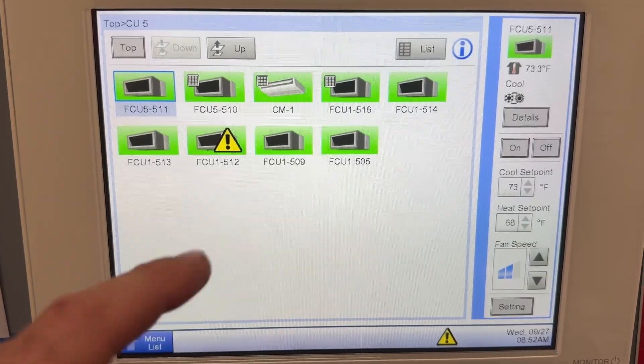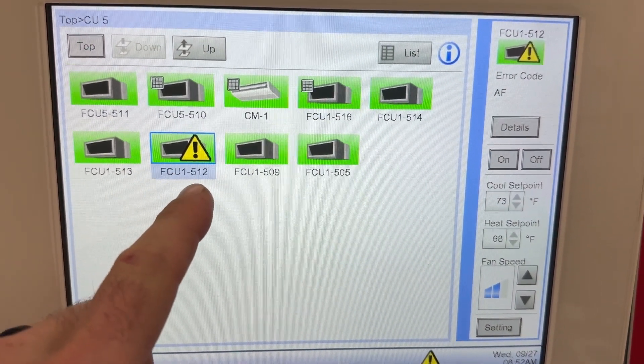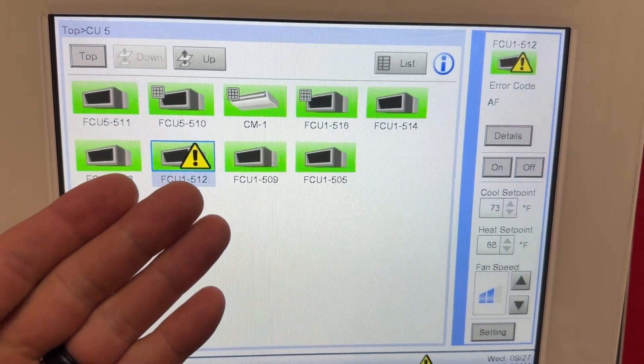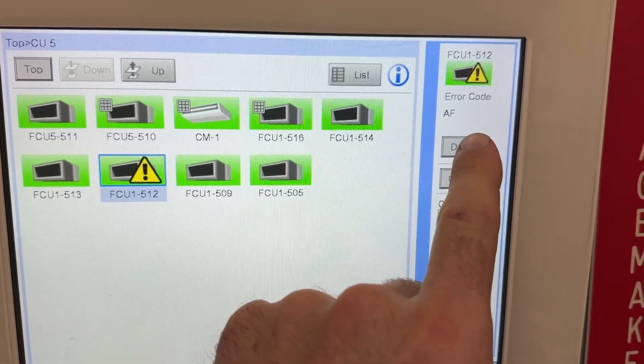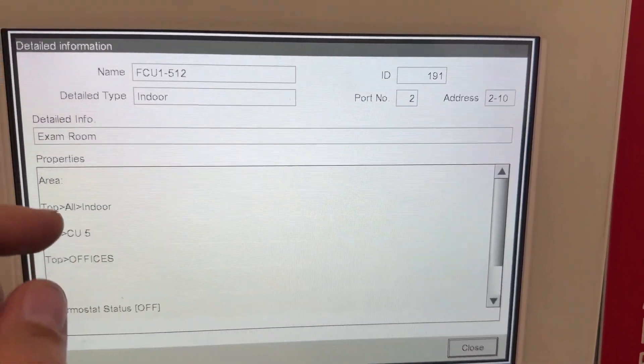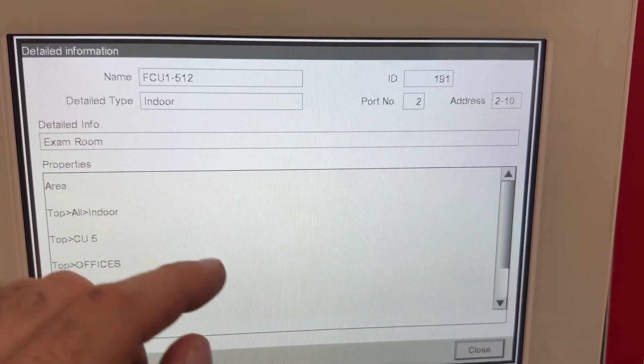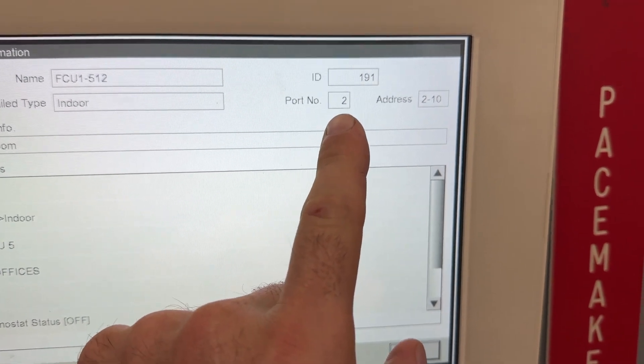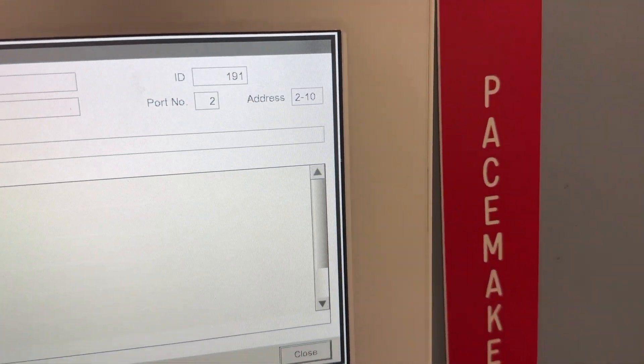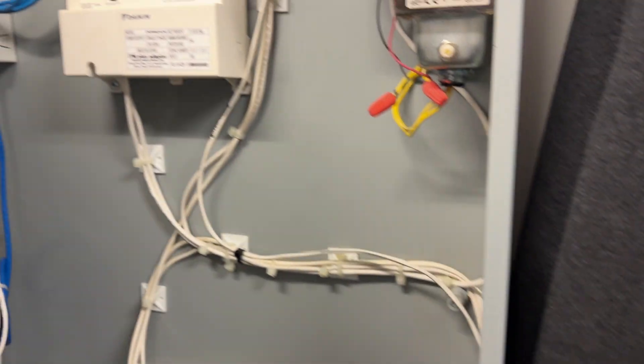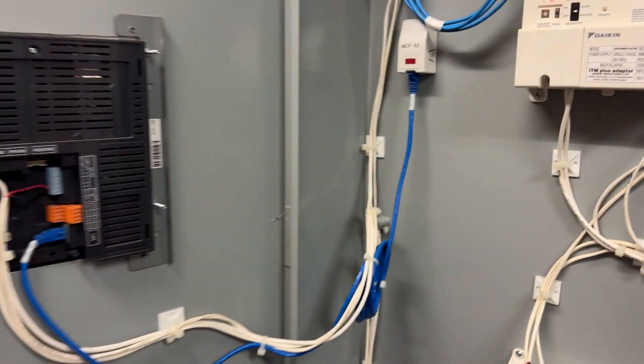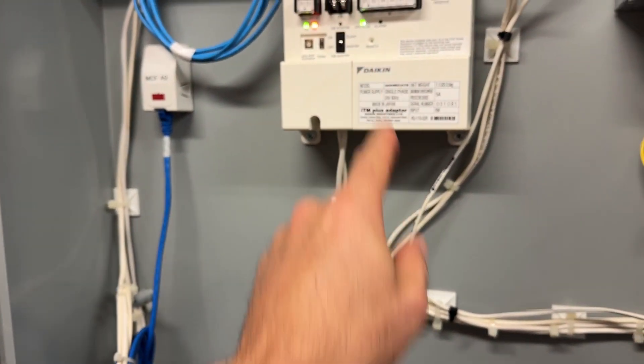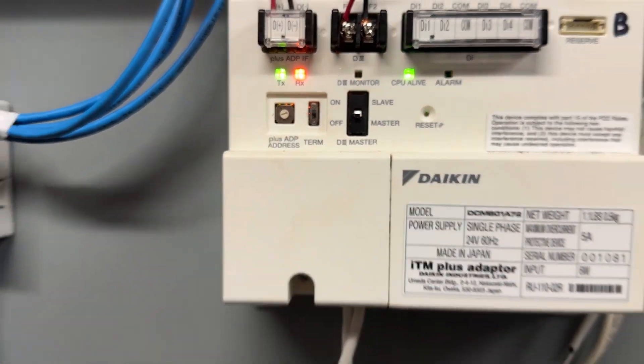Let me show one other thing. So to identify this unit because you can see all it says is 512 and there are no room labels in this building. We're gonna go to details and there's a couple things. So we do have that in details which is nice and then port 2. All that means is that if I want to tap into this system I need to be on the second module. So this is port 2 here and these are set with a rotary switch.